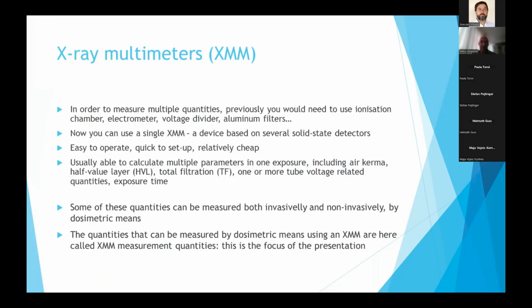I'm going to skip the general introduction and go right to the topic. You know that when you're doing quality control in diagnostic radiology, you usually want to measure several quantities, some other quantities besides air kerma. So 20, 30, 50 years ago, if you wanted to measure multiple quantities, you would need first an ionization chamber and electrometer to measure air kerma. Then if you had aluminum filters, you could use them to measure and calculate half value layer. You could also use a voltage divider to measure tube voltage, and then you could use lookup tables to estimate total filtration, etc.